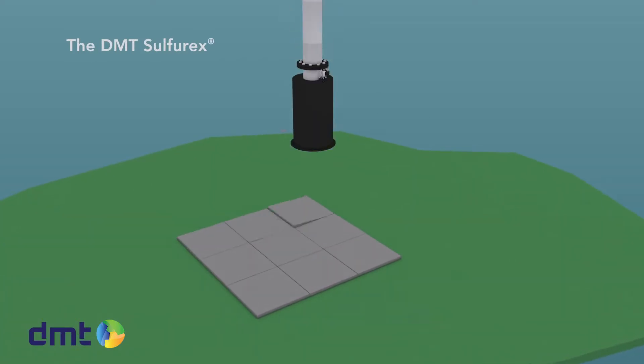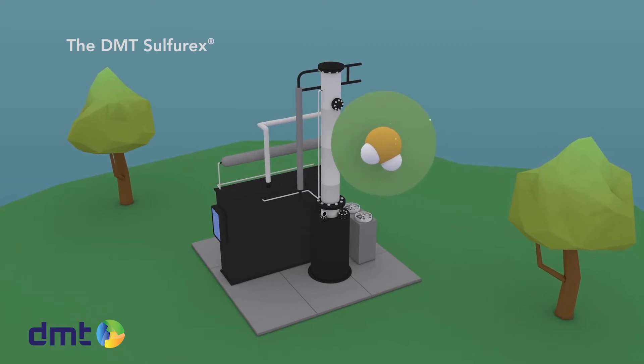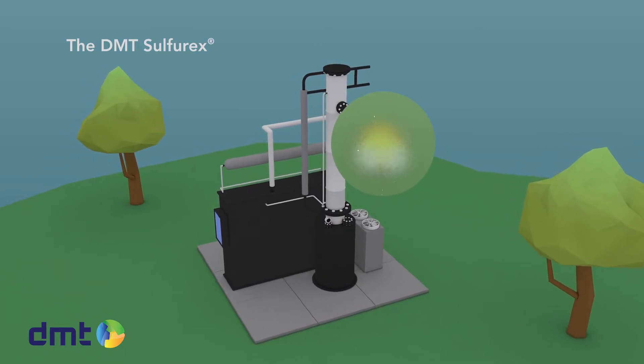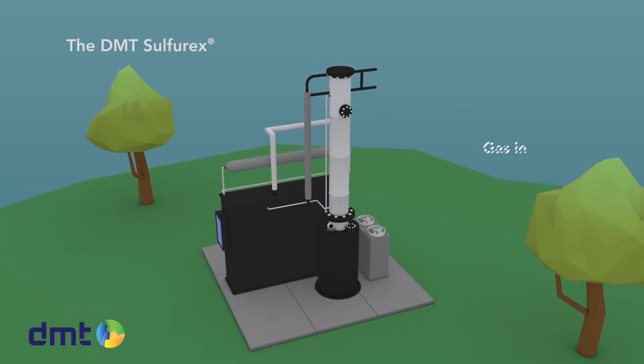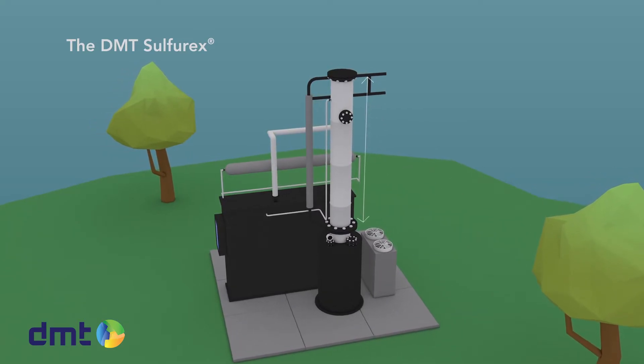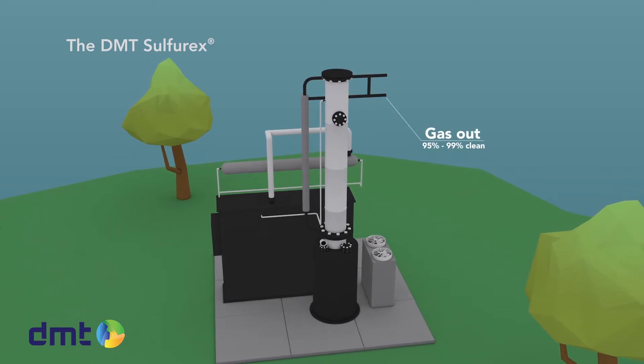H2S removal with the Sulfurex desulfurization scrubber is very effective. In this chemical scrubber, the H2S in the gas reacts with a caustic solution. The gas enters the scrubber at the bottom and flows upwards through a packed column of approximately 4 to 5 meters in height. The gas stream leaves the column almost free of H2S at the top.